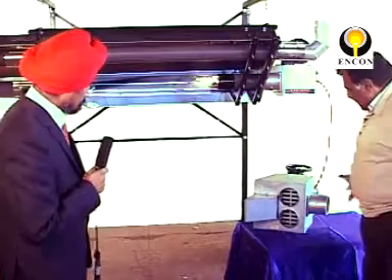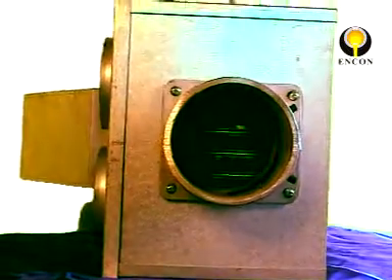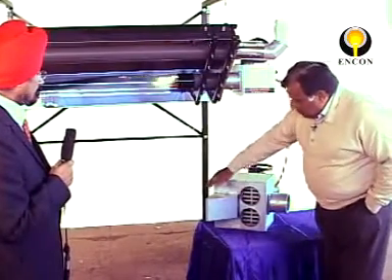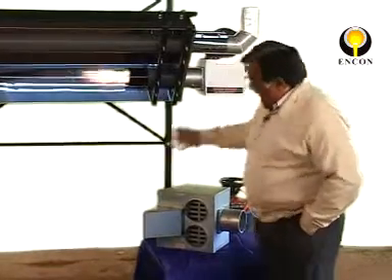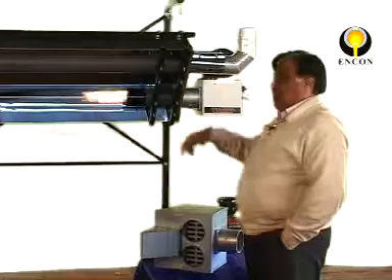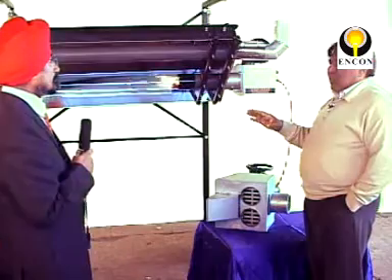In ordinary burners, the flue gases are sucked through one fan and then thrown out into the atmosphere. But here, the gases enter a heat recovery system, and from that heat recovery system they go through the free flow passage shown here. The push-through burner pushes air from one angle, and the preheated air from the other exit goes into the flame. We are preheating the flame up to around 100 degrees centigrade, which gives us a saving of roughly 5 to 7 percent.